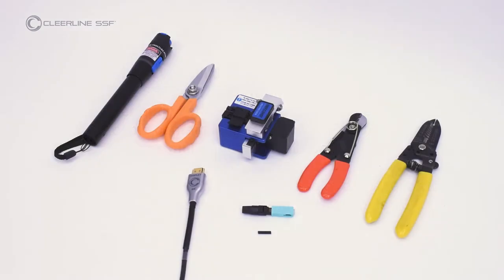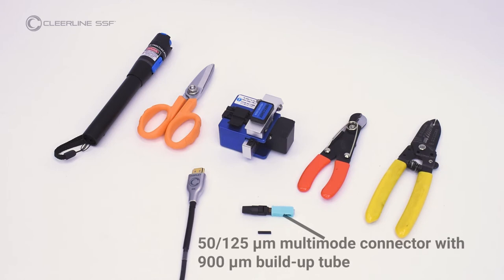Required materials are a fiber optic cleaver adjusted for use with Clearline SSF optical fiber, fiber optic cutting shears, a visual fault locator, fiber optic strippers, and wire strippers. Additionally, 50/125 micron multimode fiber optic connectors are required with 900 micron buildup tubes.